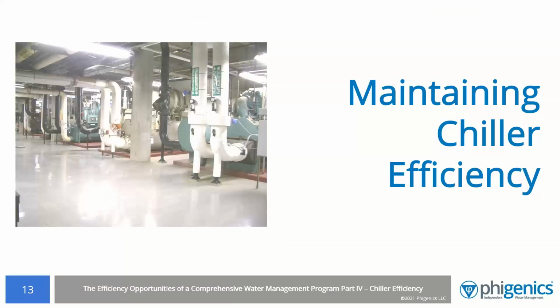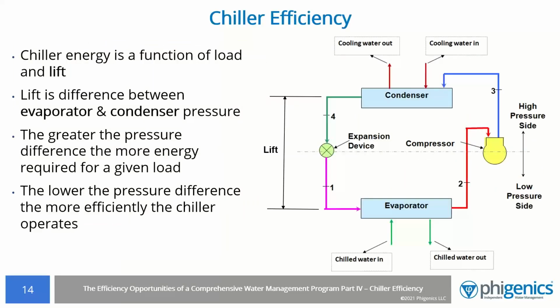Okay, the preceding slides were the 100,000-foot overview. We're now going to dive into some of the issues that impact chiller efficiency. This is not a physics course, so don't tune out just yet, but it is important to understand on a very basic level the physics of your HVAC system. Chiller energy is a function of load and lift. Load refers to the cooling demand on the chiller. Lift refers to the difference in pressure between the refrigerant in the condenser and the refrigerant in the evaporator. The greater the pressure difference, the more work that the compressor is having to do, or energy that needs to be added to the process in order to meet the demand for a given load. We will come back to this relationship, but we will leave the physics out of the next few slides.